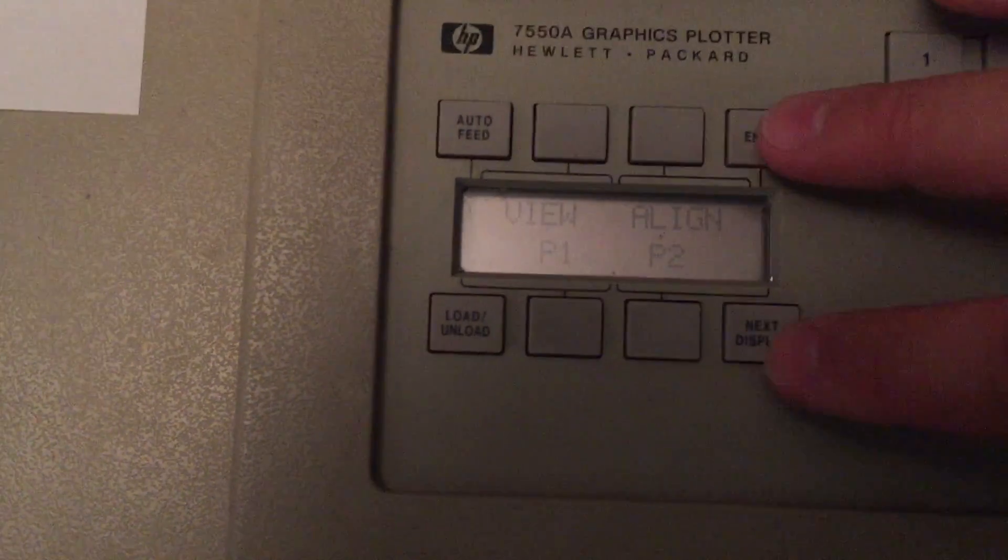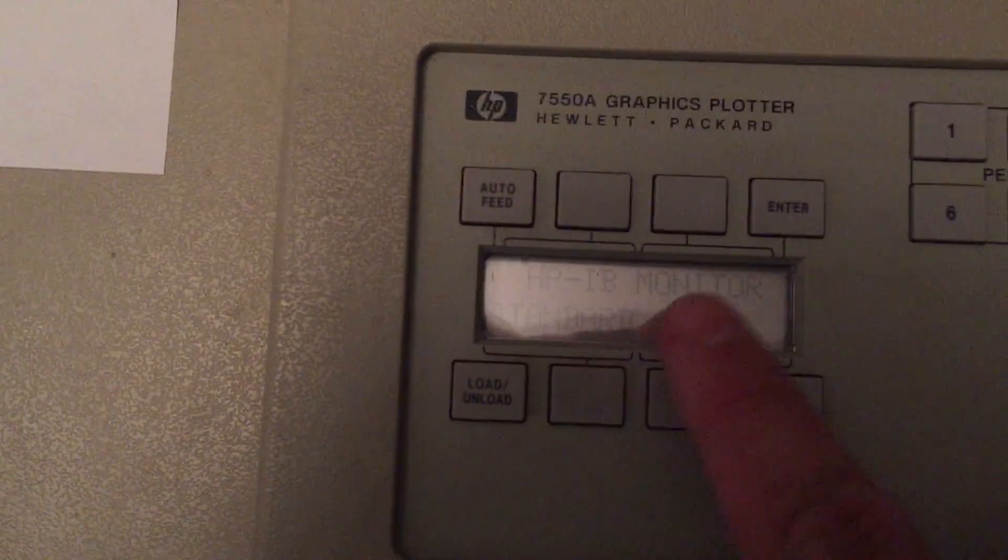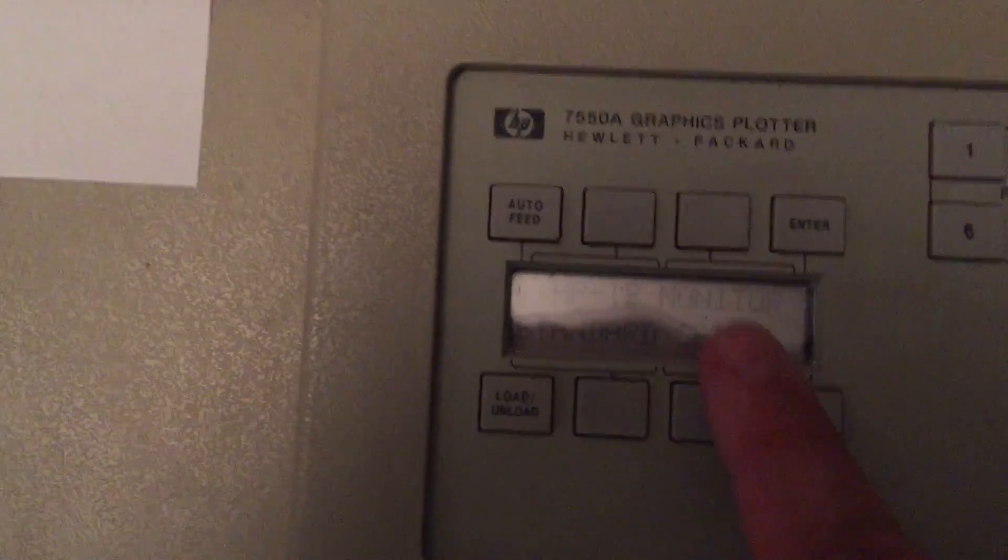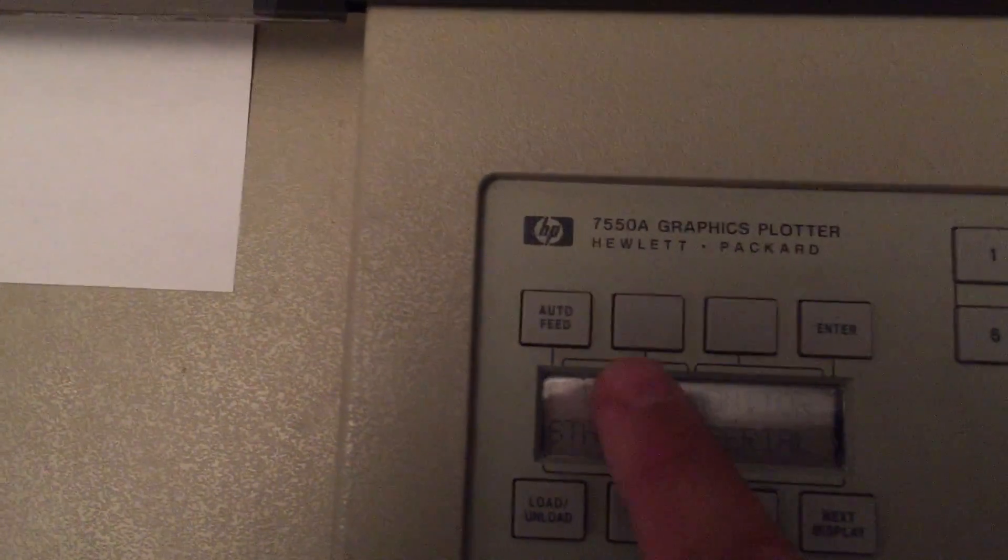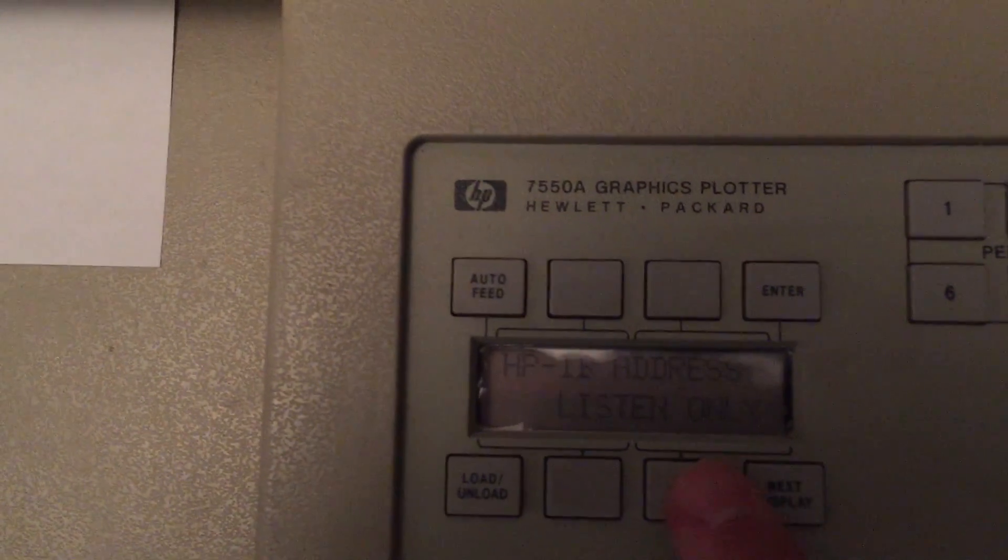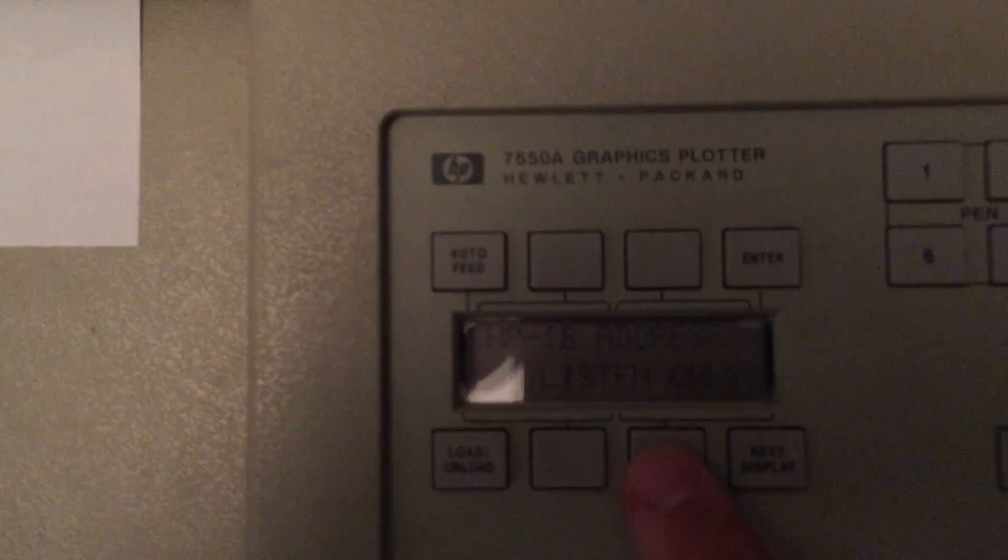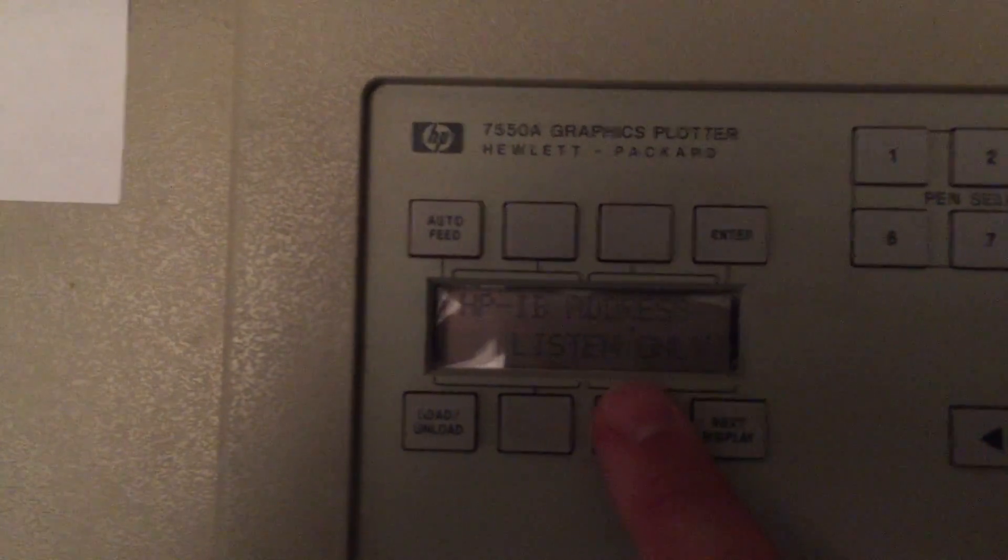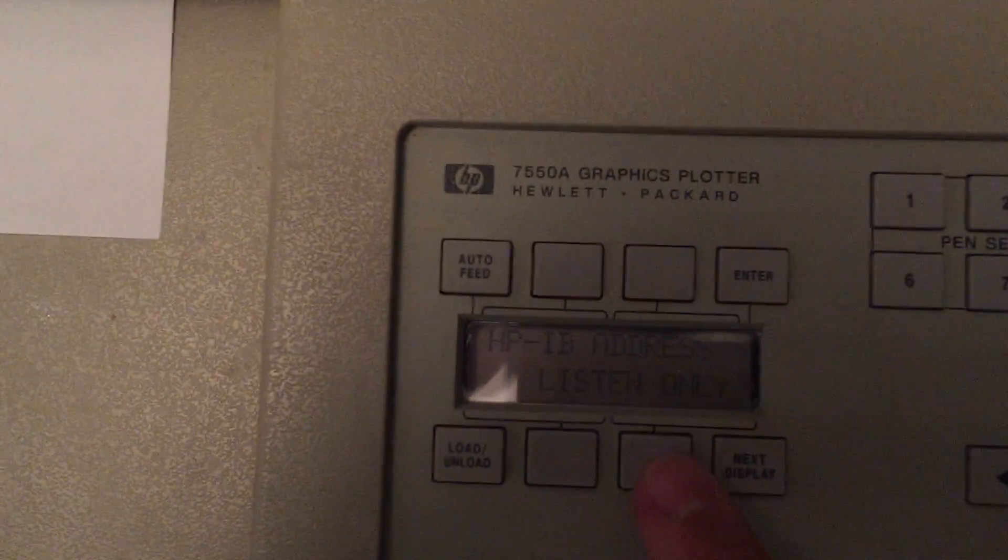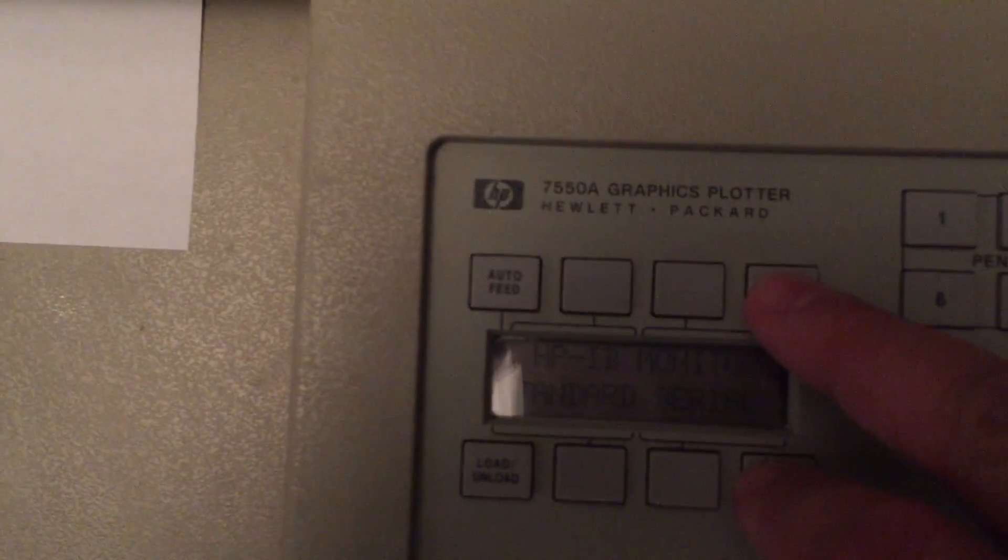To go into the sub menus, you hold enter and push next display. It goes into HP-IB and there's monitor and standard mode and serial - these are all the different things you can configure. Right now we're just concerned about HP-IB, so I'm going to hit that. I've got it in listen only mode. You can toggle through, there's over 30 addresses you can use. When you hit the mode you want, you hit enter and that accepts it into the settings.